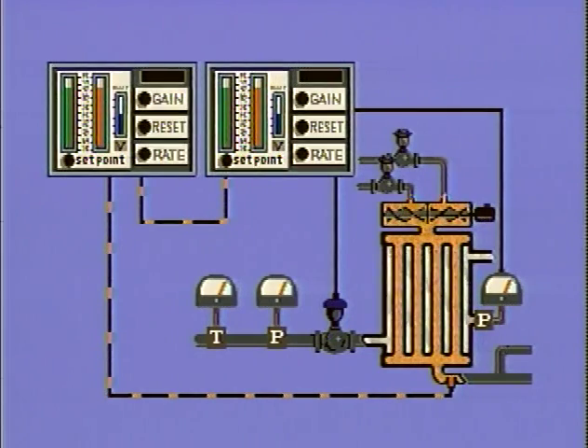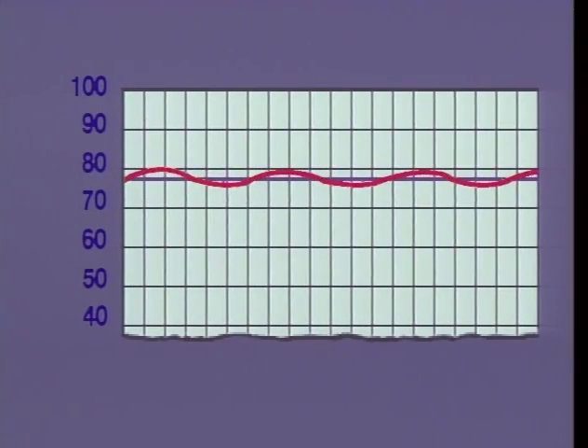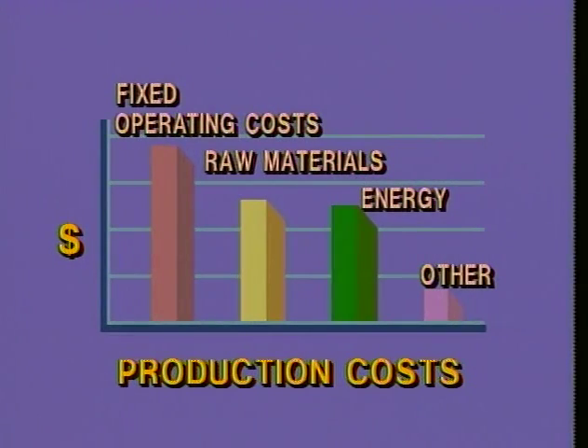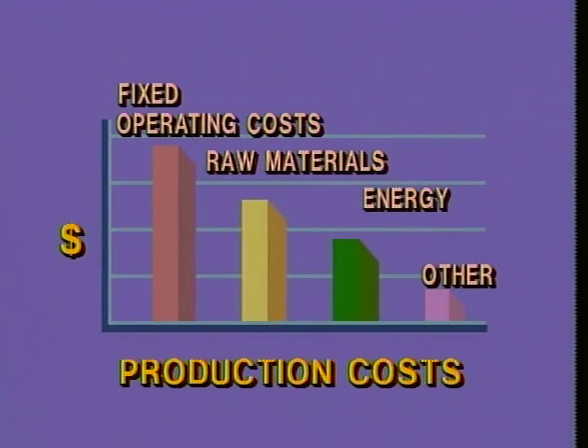Here is how the product's temperature record looked after cascade control was added to the system. Once each controller was tuned to the system, the temperature varied only 2 degrees above and below the set point, instead of 5. This allowed the set point to be lowered to 77 degrees and still keep the temperature above the lower limit of 75 degrees. The result was a reduction in the amount of energy needed to run the plant, and therefore a savings in the cost of making the product.